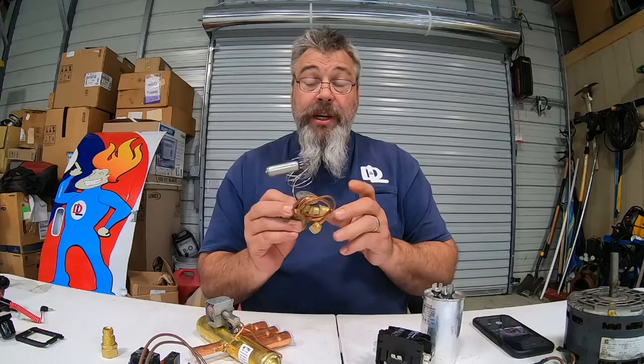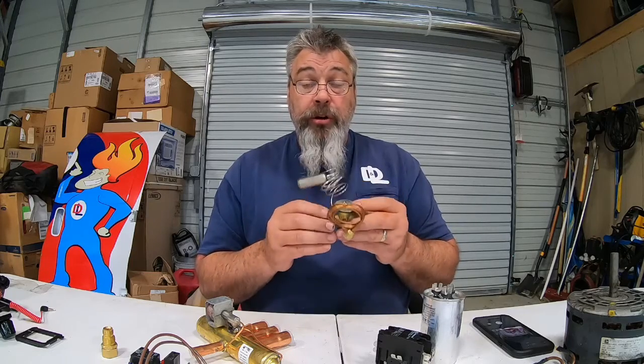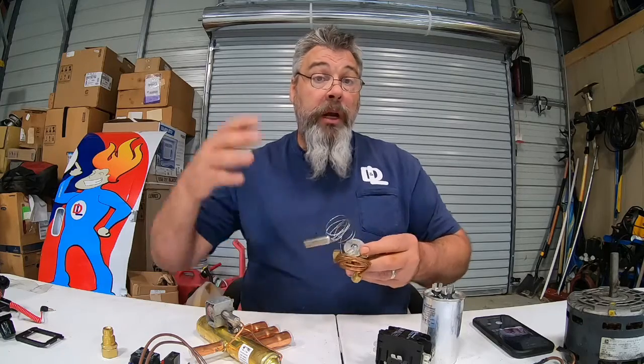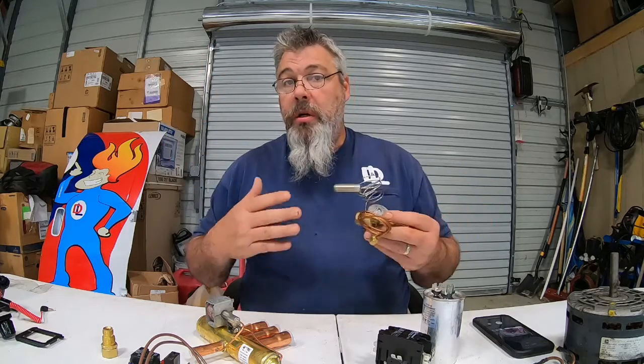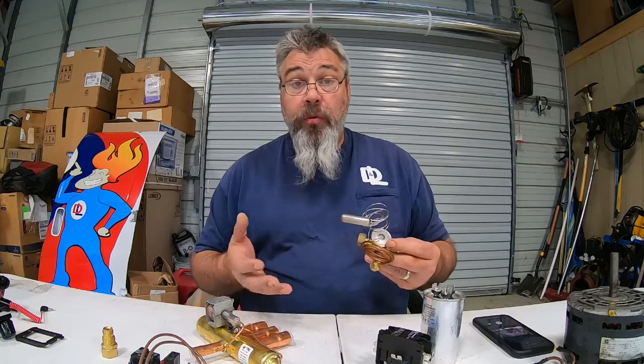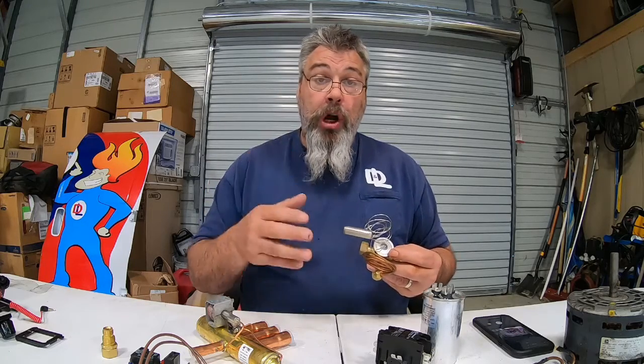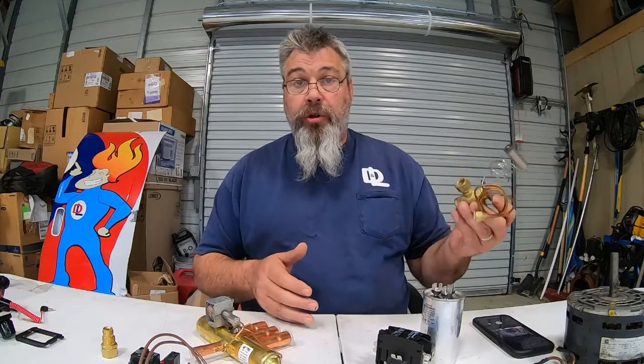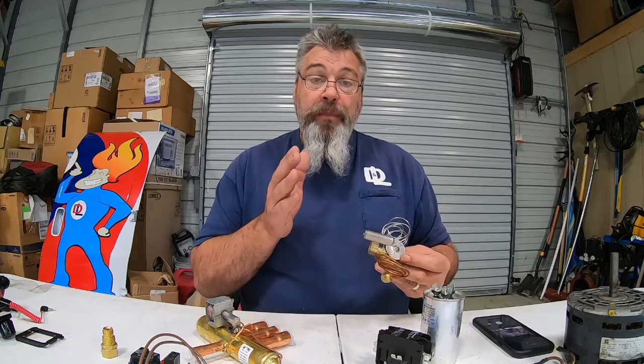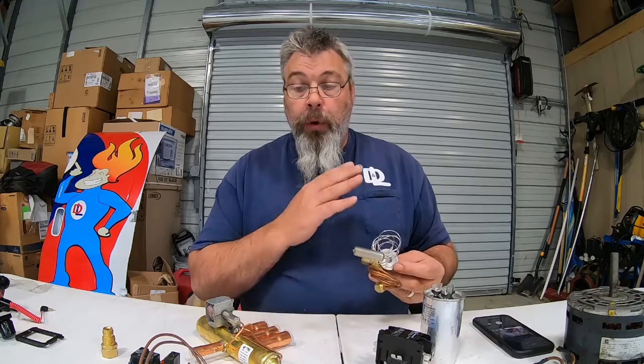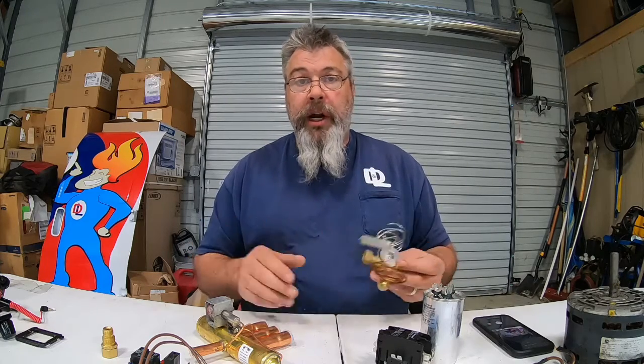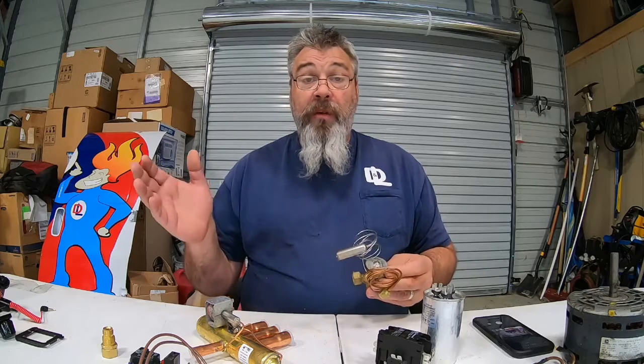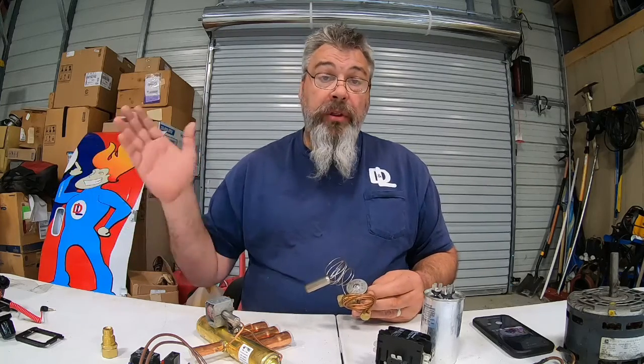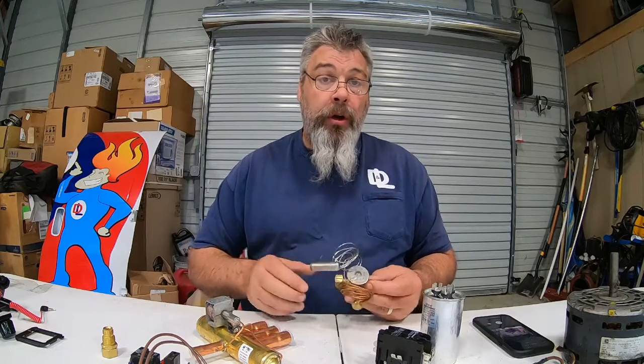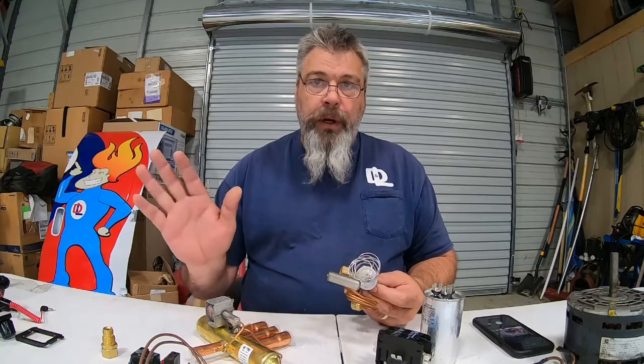A lot of manufacturers are using these to get your SEER ratings and your energy efficiencies up. They're also building bigger coils, monster systems, because they hold more refrigerant. The new refrigerant, which is 410A, we'll talk about in a different video, because the old refrigerant is R22, which as of January 2020 will no longer be manufactured in the United States. It can be manufactured outside of the United States, but they have not allowed us to bring it in from any other country either. Don't worry, don't get all scared, just a brief explanation.